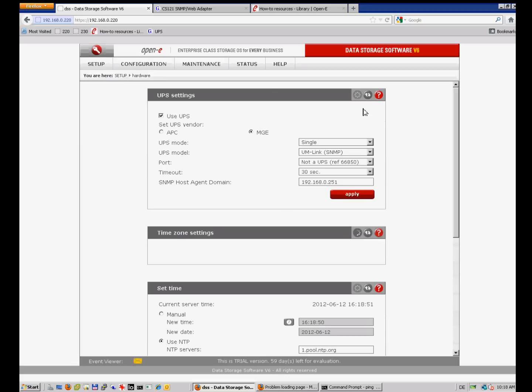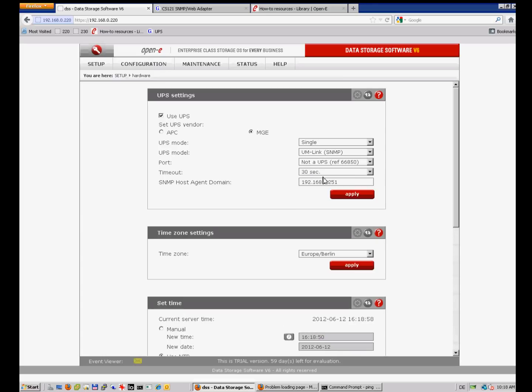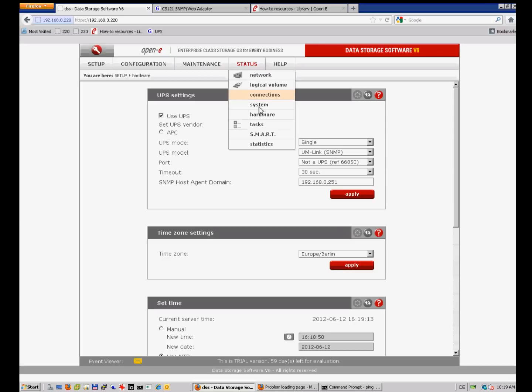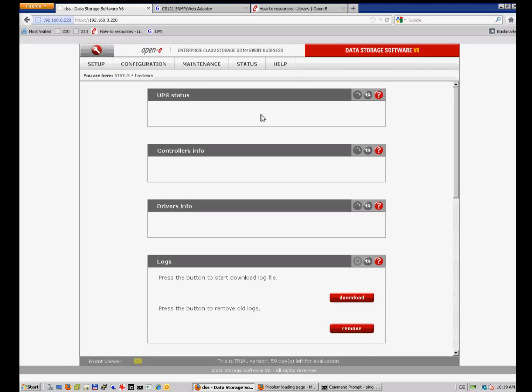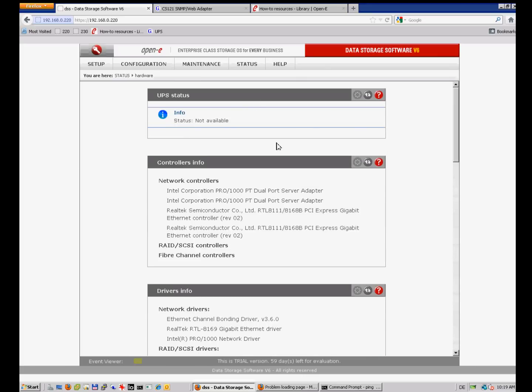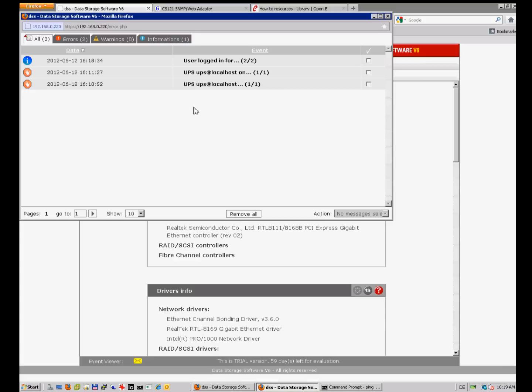The UPS settings in DSS are found under Setup > Hardware. As mentioned, my timeout was set to only 30 seconds. When I switched off the power, 30 seconds passed and a shutdown signal was already sent to DSS. Let's look at the Status > Hardware section.